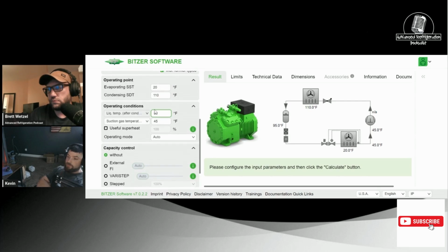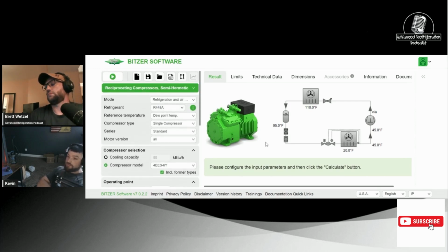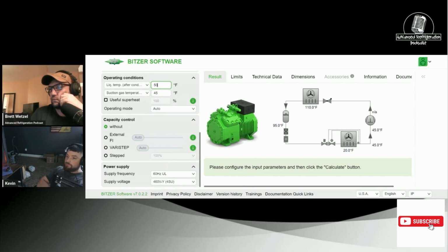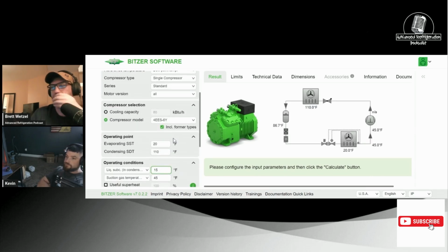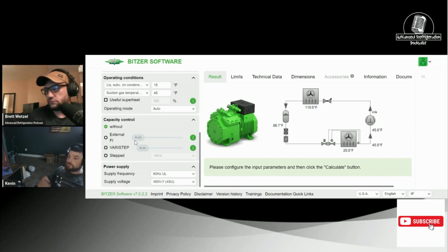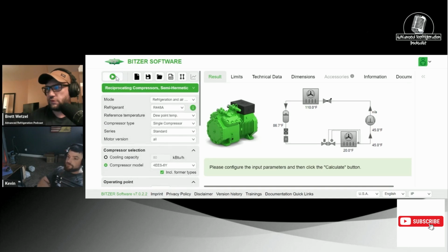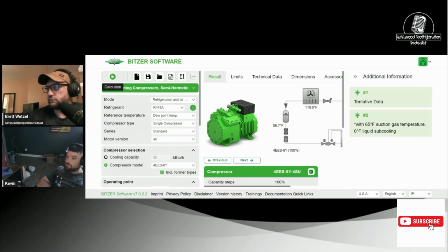Now, this is what I do anytime I'm testing compressors to see what their efficiency is. Meaning, if you were to take the amp draw, Brett, and you raised it to a plus, say, 25 SST, left the head alone. Leave the suction alone. No, I'm putting this back to the way it was. Okay, so what do you want me to do? Put it to a plus 25 SST. And this is also the same theory behind floating the suction. Watch what it does to the amp draw of the compressor.